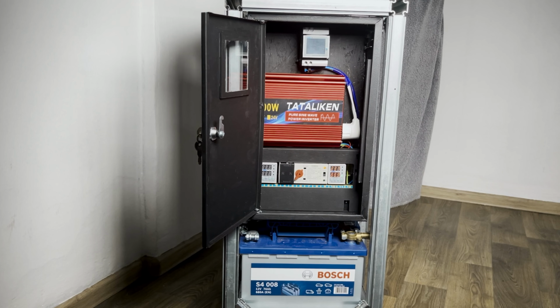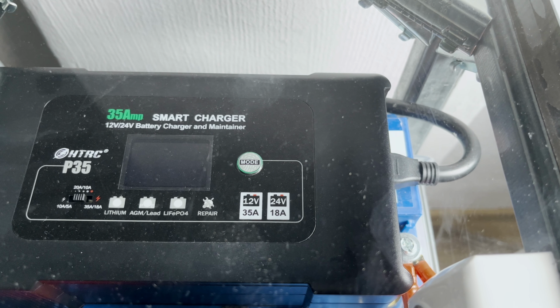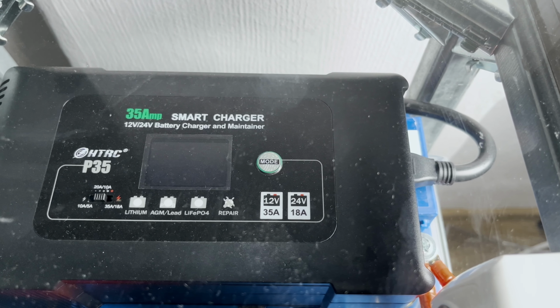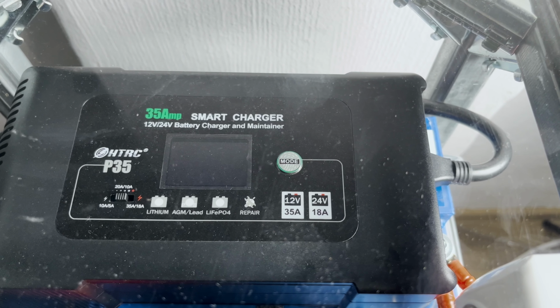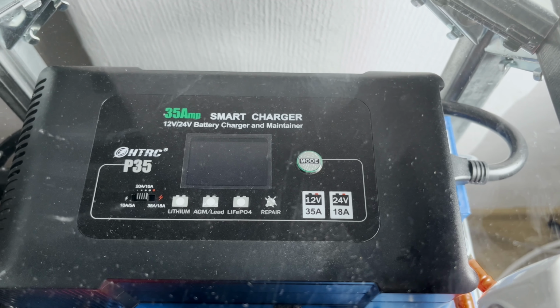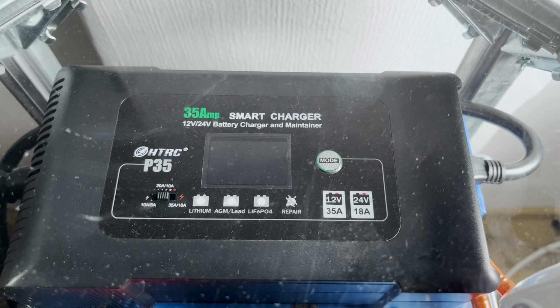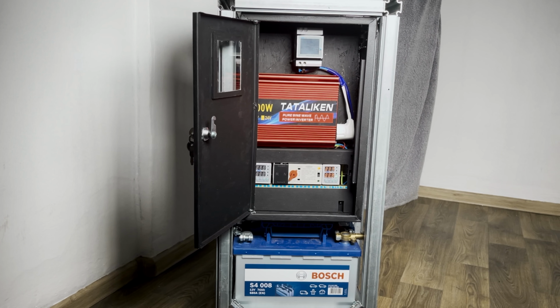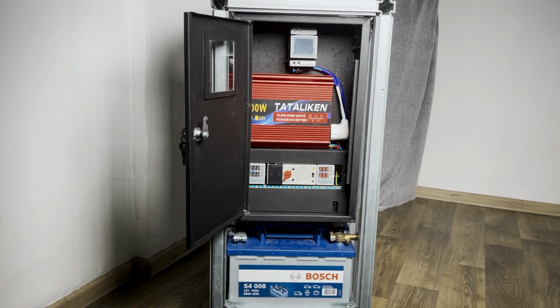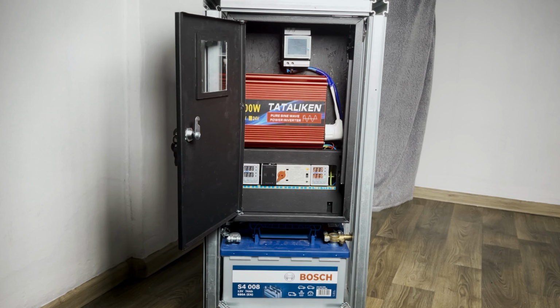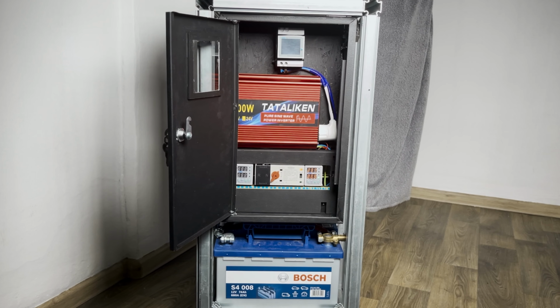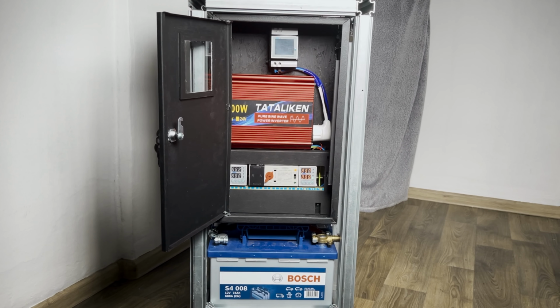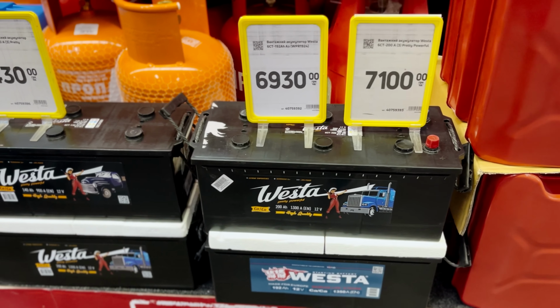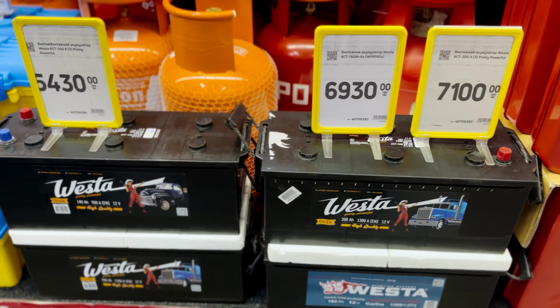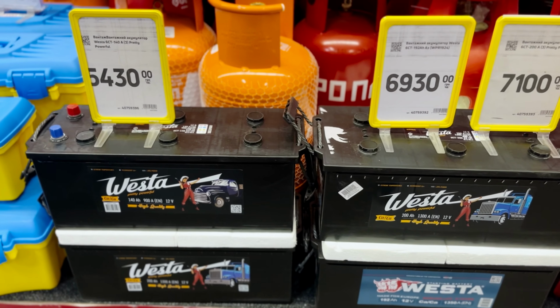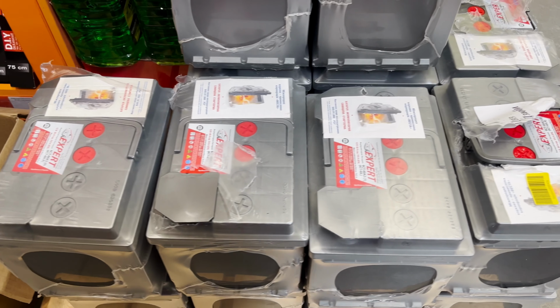In this build, the charger has a reserve. It is also possible to add another 1 to 2 batteries without any issues and switch to a charging current mode of 35A instead of the current 20A. In fact, I plan to do this if the situation with electricity worsens in winter. As you can see, the most expensive component of this assembly is in fact the batteries themselves. But if you have the opportunity to install the system in a non-residential well-ventilated space, you can use regular serviceable lead-acid batteries, which are almost half the price.